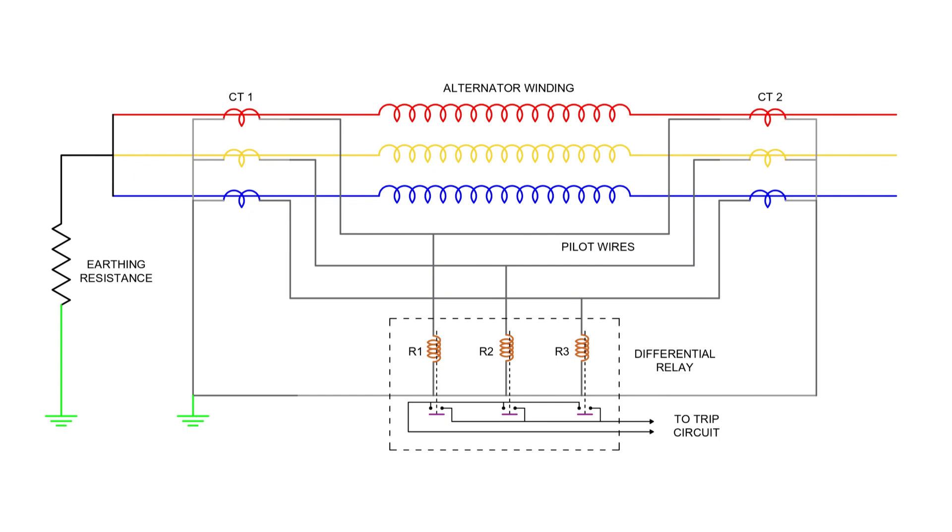The secondaries of each CT set are connected in star, and both star points are joined using a four-core pilot cable. This ensures that each pair of CTs has an independent circulating path, allowing accurate current comparison.